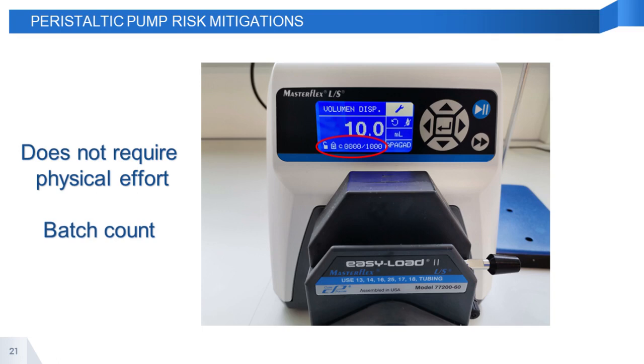If after the pump finishes dispensing those 1,000, there is an empty vial, it means that the operator has dispensed it twice into one of them. And also the other way, if the pump says we still have some dispensations to make and we do not have more tubes to fill, it means we have skipped some of the tubes, and therefore there are some empty tubes. So we can solve the problem at the moment, and we do not need a weight control anymore, saving a lot of time. So that would be my part.